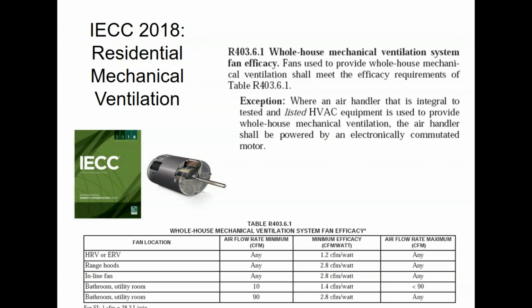If you're using a different type of system to bring the air in, then there's some specifications down on the bottom of the screen there on how efficient that piece of equipment would have to be. So I said you could do exhaust only, bad idea. Supply only, most common. You could also do a balanced system where I have exhaust going out and supply coming in. And the idea there is I keep the house pressure neutral compared to the outdoors, and I don't have any problem with wind coming in and things like that.